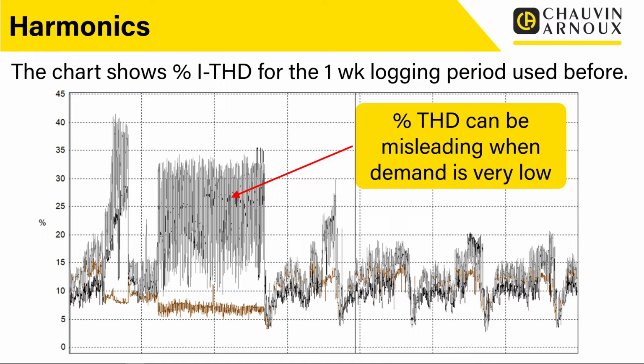But if we wanted to look at this plot to work out what's a reasonable percentage current THD to apply for this installation, if you look at the normal working days, what you'll see is somewhere between maybe 10% to 15% probably captures the regions. We have got parts that go out towards 20%. So if we're trying to capture everything, we could be up towards 20% maybe, if we're trying to cover the full range. But if we went for 15 as a typical value, again, we're in that sort of bracket. So that's still quite a big percentage of the current that is present in the harmonics.